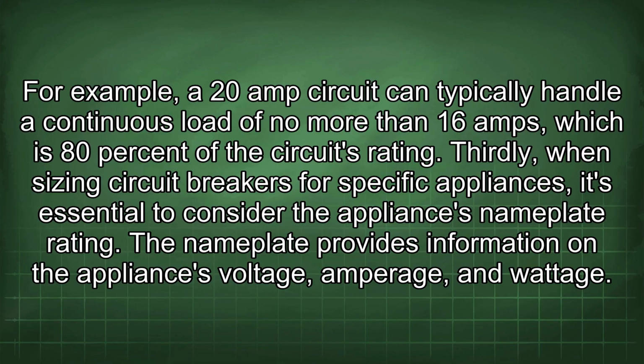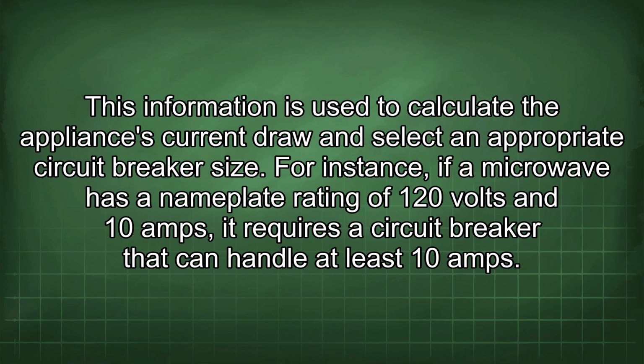Thirdly, when sizing circuit breakers for specific appliances, it's essential to consider the appliance's nameplate rating. The nameplate provides information on the appliance's voltage, amperage, and wattage. This information is used to calculate the appliance's current draw and select an appropriate circuit breaker size. For instance, if a microwave has a nameplate rating of 120 volts and 10 amps, it requires a circuit breaker that can handle at least 10 amps.